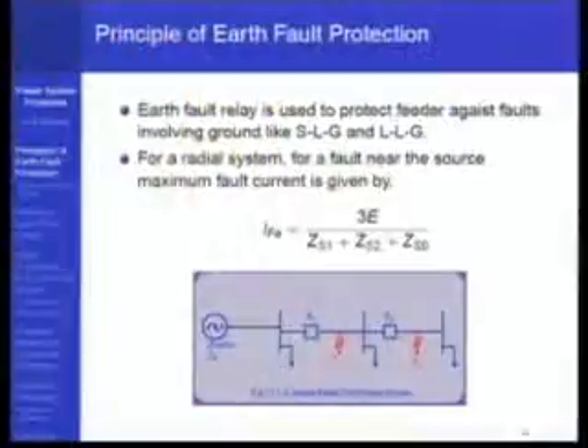And to reduce it, to bring that magnitude within a reasonable range, you can use a grounding impedance. So the generator can be grounded through a certain impedance. If that current tends to be very large, then you would need a grounding impedance Zn, so that this fault current is reduced. So that is how. So it's not like that.